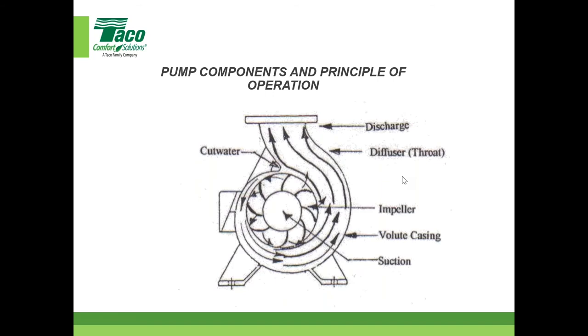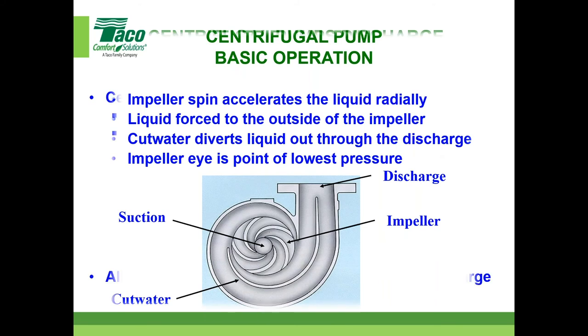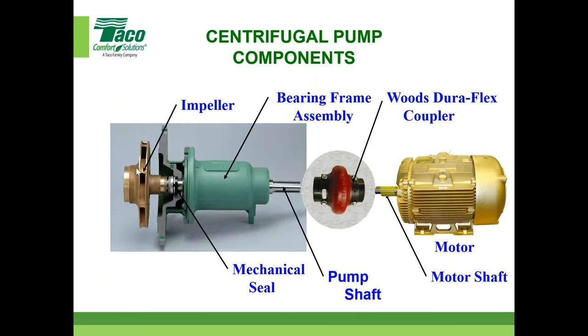I do know that the impeller thickness does change with different impeller designs. I do not believe that there is a standard in the industry, but it's such a great question. I'm going to do a follow-up this week and see if I can find out if there are any standards in the industry. Here's a picture of an impeller. You asked about thickness, and you can kind of see it. That doesn't look more than a quarter inch, maybe 3/8 inch, maybe even a little less on the shrouds, right? The kind of enclosures of the two. Obviously, there are other places where it's a lot thicker, but probably the most important part is that piece there.